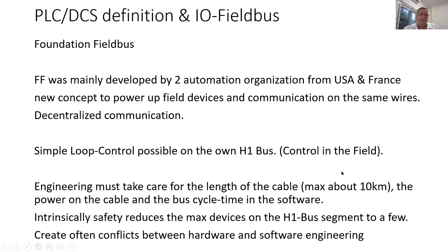This is one point, but you have to look also at the software side, at the bus cycle time. That means how often we can exchange the data. If you think of it like a cake, then you have maybe 1 second, which is the time of the cake. And every device needs some time to execute itself, to get the information from the physical sensor and prepare it for the bus. And it also needs time to send the data on the bus so that everybody can read it. And if you don't take care of this bus cycle time, then you automatically get a slower process response.